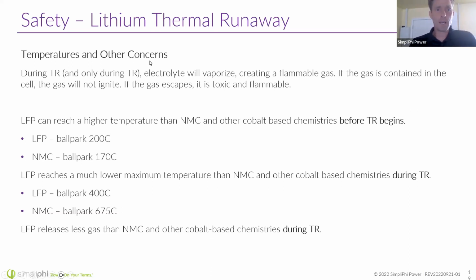So there are a couple things to talk about with temperature. During thermal runaway, electrolyte can vaporize, and this only happens when it gets so hot that the liquid electrolyte can turn into a gas. And if this gas is contained within a cell, that cell can rupture a vent and cause that gas to escape, and that gas can burn. That gas is toxic, and it's more toxic depending on which type of chemistry you have. But the point to note is that for LFP cells, they can reach much higher temperatures without thermal runaway beginning. So about 30 degrees Celsius hotter, 200 degrees Celsius versus 170. LFP also has a much lower maximum temperature when off-gassing happens during a thermal runaway.